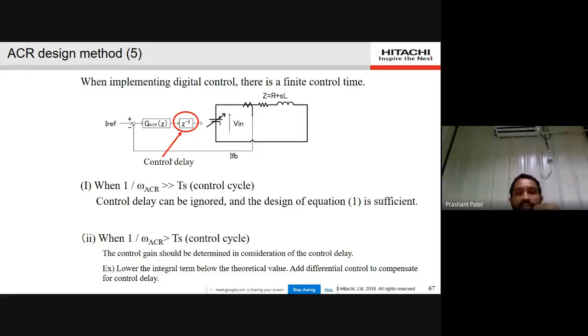One consideration: suppose your speed, 1 by omega ACR, is very much greater than your sampling time, then I think you can ignore the delay. But if it's not very different, just slightly higher than TS, then we have to consider this delay. Normally we can consider this delay as 1.5 TS. I think we are familiar with the delay of the PWM inverter, so just put this delay block in the simulations and verify your ACR loop.